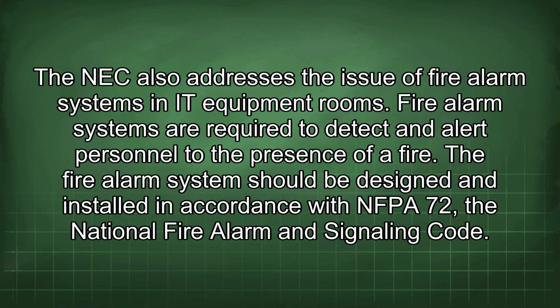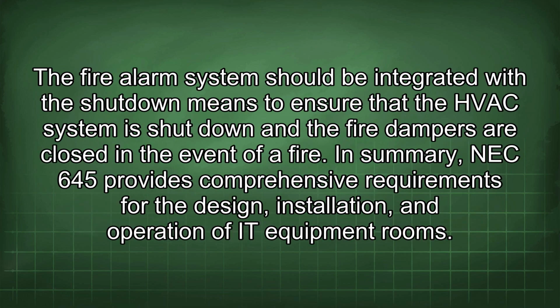The NEC also addresses the issue of fire alarm systems in IT equipment rooms. Fire alarm systems are required to detect and alert personnel to the presence of a fire. The fire alarm system should be designed and installed in accordance with NFPA 72, the National Fire Alarm and Signaling Code. The fire alarm system should be integrated with the shutdown means to ensure that the HVAC system is shut down and the fire dampers are closed in the event of a fire.